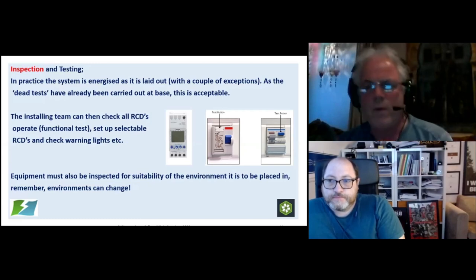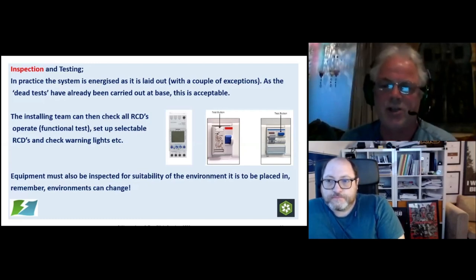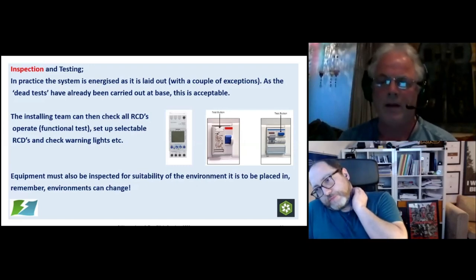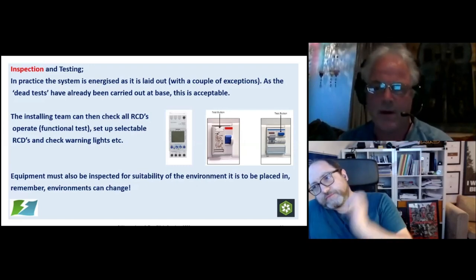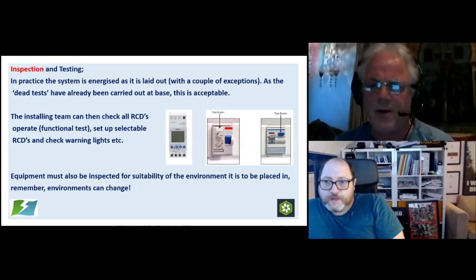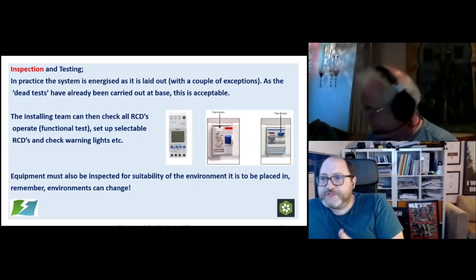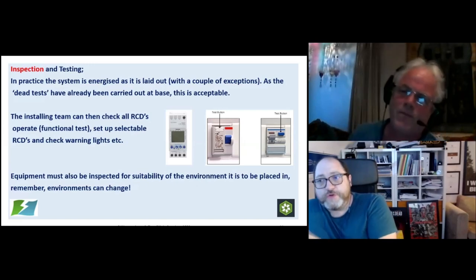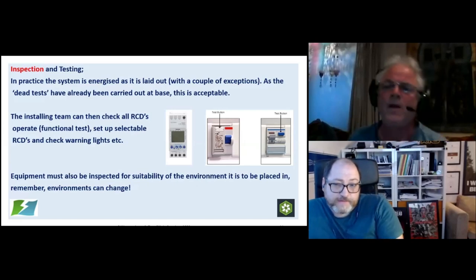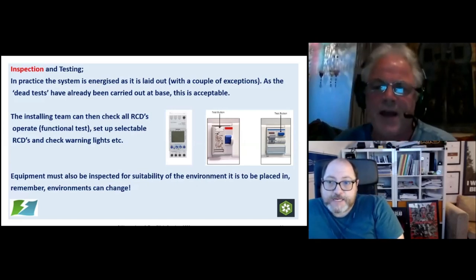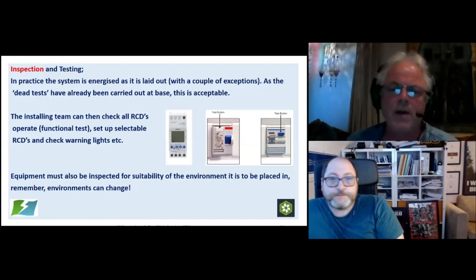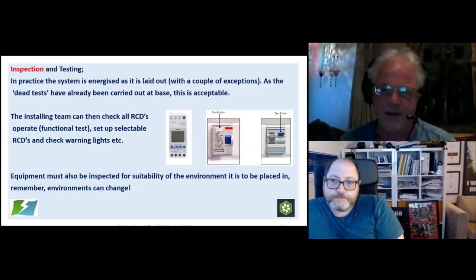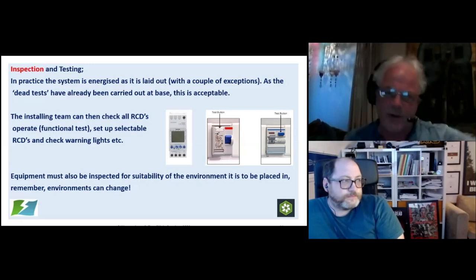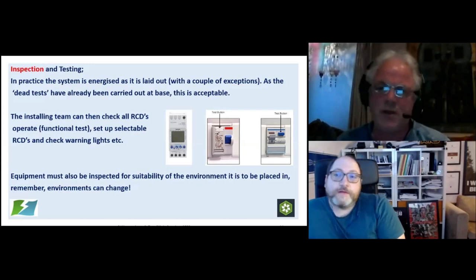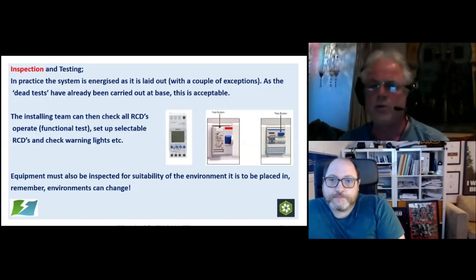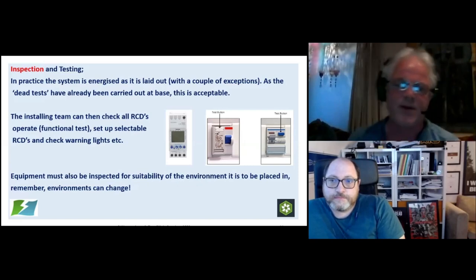There's nothing wrong with having an RCD. And I think this is one of the things that installation electricians especially get a little bit, the idea of having a 1 amp RCD with a 1 second delay on it, they think, oh God, is that going to do anything? Well, obviously we assume the RCD is there to protect life, for the purpose of additional protection. But it's not there for that purpose here. We're looking at protecting distribution equipment and stuff like that with these larger sizes of RCD. So it's something we've got to get used to when we're dealing with temporary systems. We've got to get used to having that selectivity all the way through and using those larger levels of RCD protection. There's nothing wrong with it as long as we conform with the requirements of 7909.